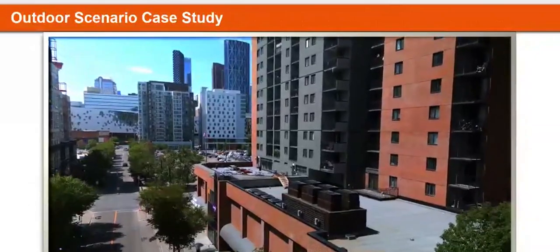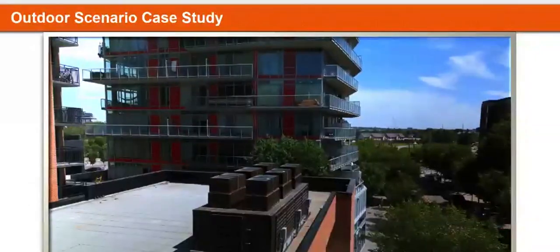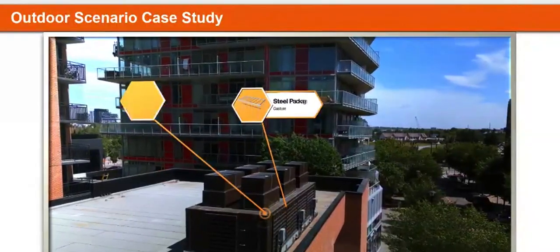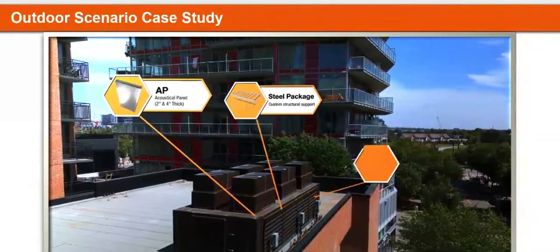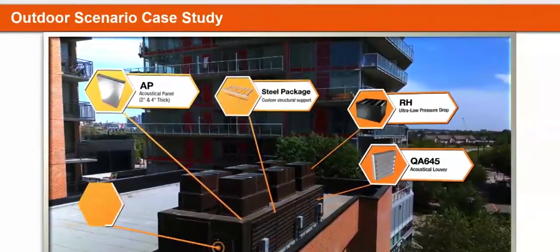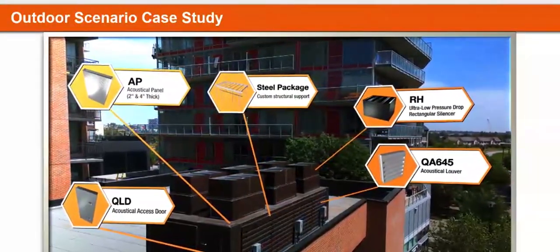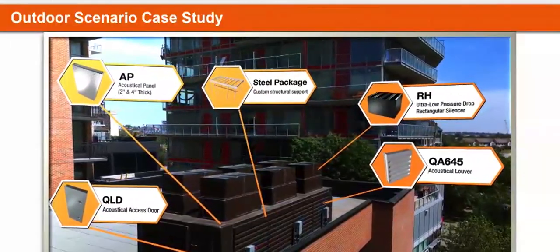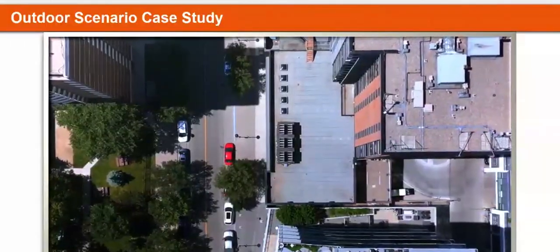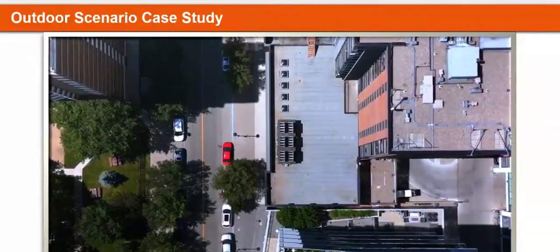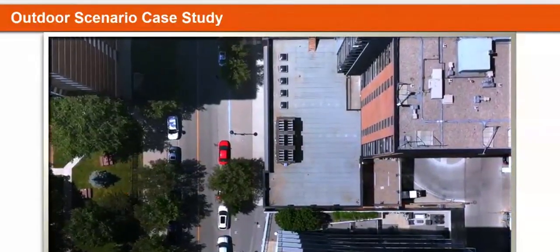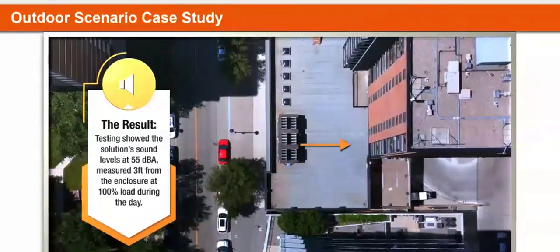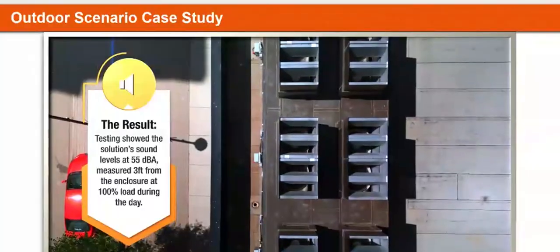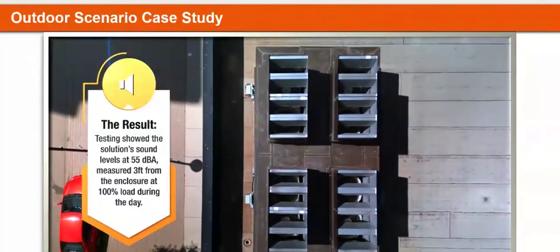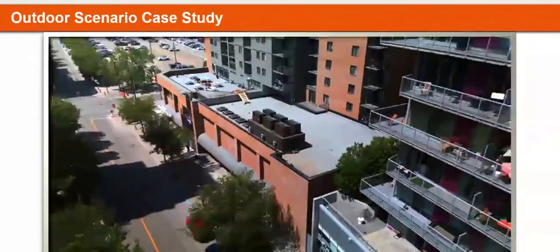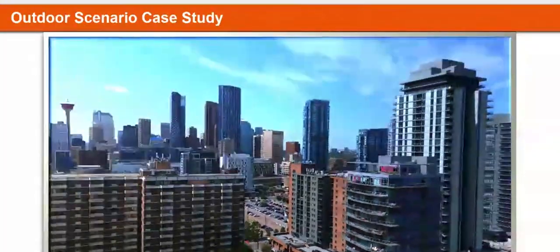The team designed and implemented a Price Noise Control acoustic enclosure that consisted of a structural steel package, 2-inch and 4-inch thick acoustical panels, QA645 acoustical louvers, RH silencers, and an acoustical access door. 4 weeks after installation, the Price Noise Control Team conducted a site survey to verify the results predicted by the Price Acoustic Analysis software. The testing showed the solution's sound levels at 55 dBA, measured 3 feet from the enclosure, with units running at 100% load during the day. This project shows Price Noise Control's expertise in delivering science-driven noise control solutions, demonstrating the value of working with a reputable manufacturer.